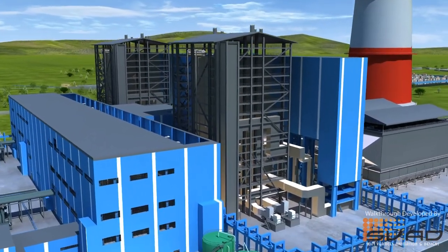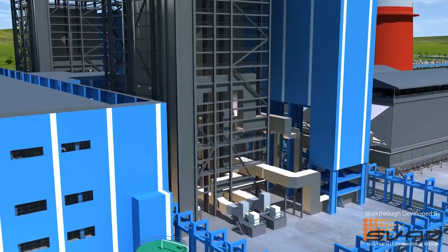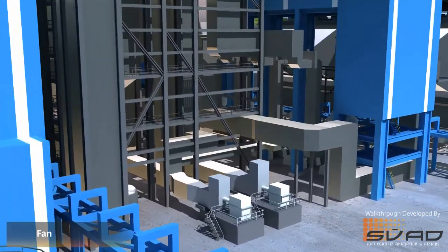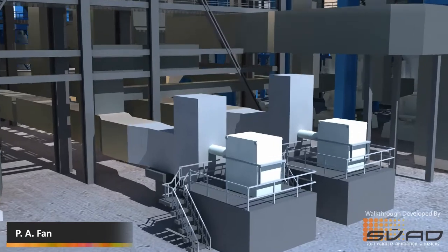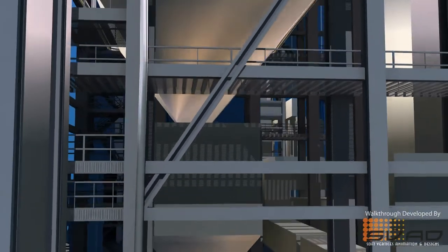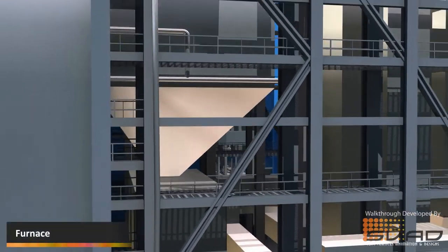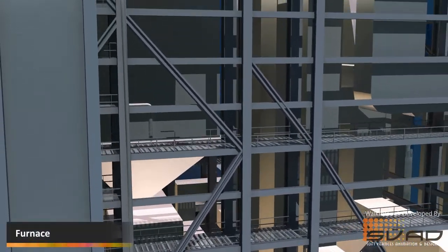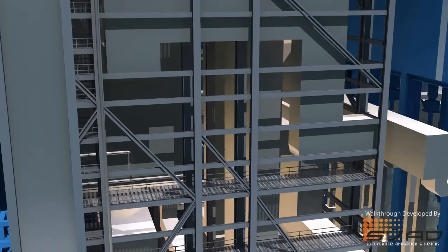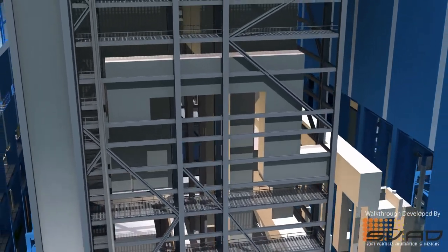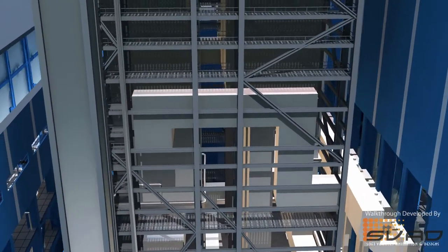PA fans are the large high-pressure fans which supply the air needed to dry and transport coal directly from coal mills to the furnace. As soon as the coal enters the furnace, it instantly catches fire and burns with high intensity to produce heat. The temperature inside the furnace is around 1300 degrees Celsius.